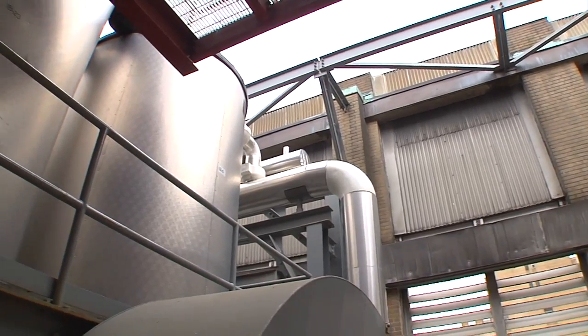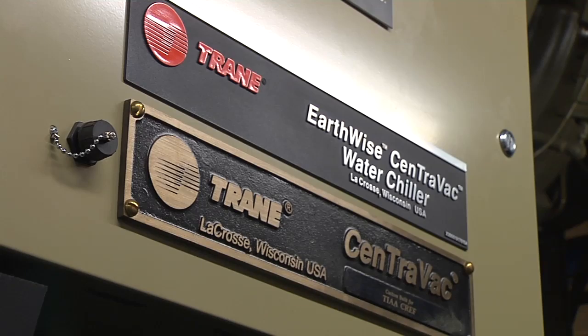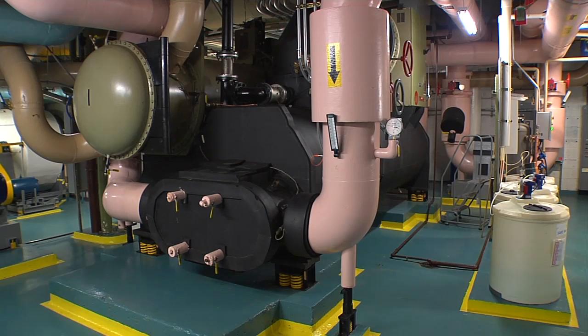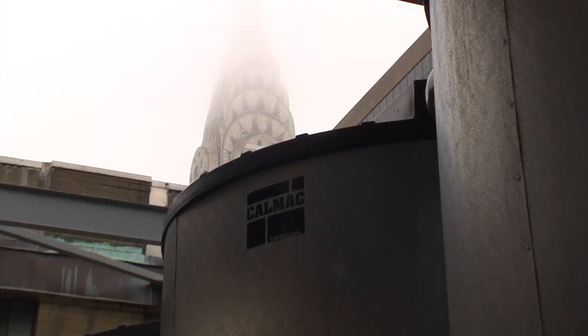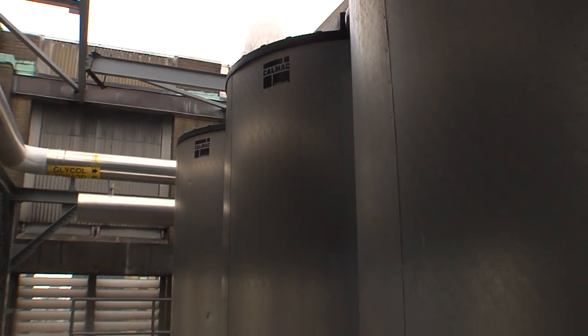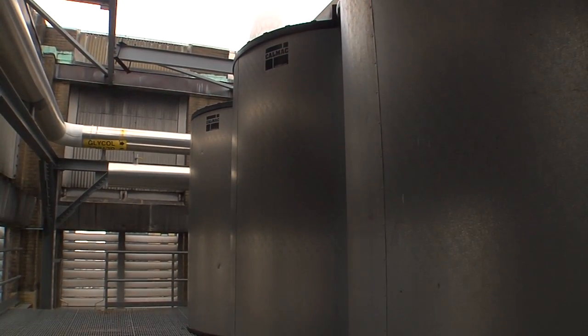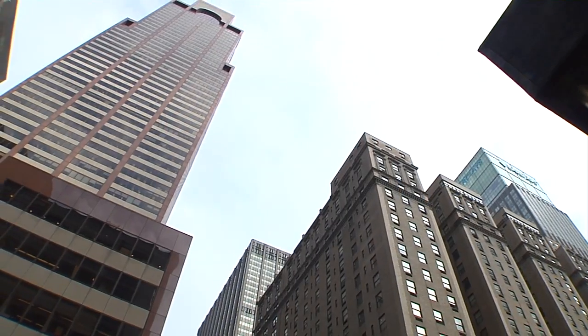It's about 6 o'clock in the evening, the chiller goes on, and we build ice. By midnight or so, we have 30 full tanks of ice upstairs. In the daytime, we run this machine until about 8 o'clock in the morning to pre-cool the building, then switch over to the ice plant and run on ice pretty much all day. We've seen a reduction of about $700,000 a year in utility operating costs.